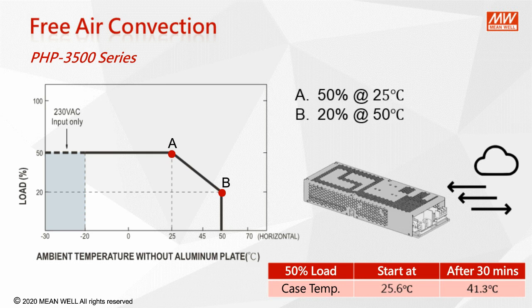The PHP 3500 can output 50% load at up to 25 degrees Celsius, which is point A on the curve, and can operate at temperatures up to 50 degrees Celsius, but with load derated to 20%, which is point B on the curve. For cooling effectiveness, we're measuring a specific case temperature hotspot on the enclosure. After 30 minutes of operating at 50% load at room temperature, the case temperature rose to 41.3 degrees Celsius, which is a 15.7 degree Celsius temperature rise.